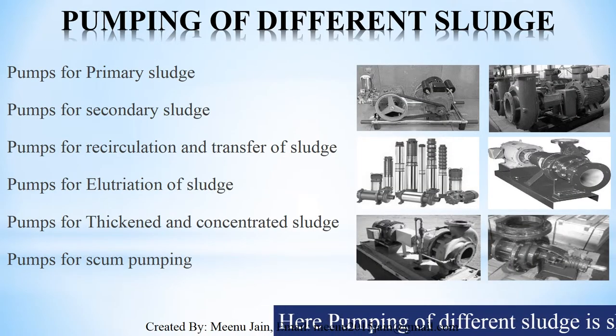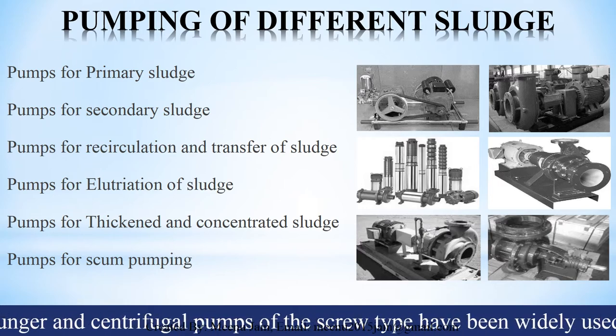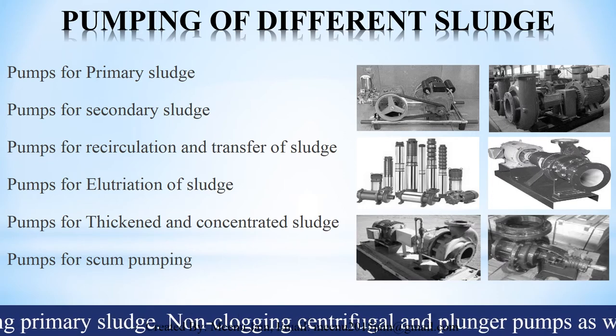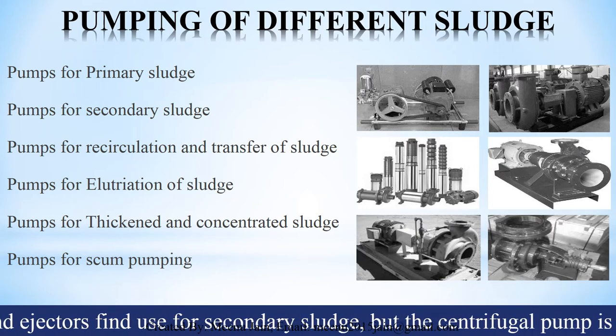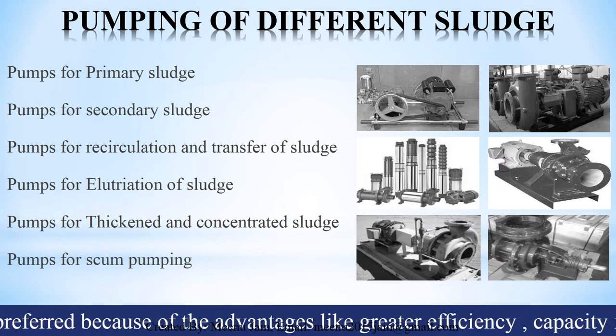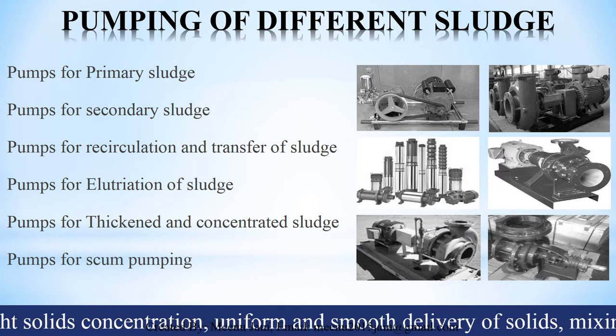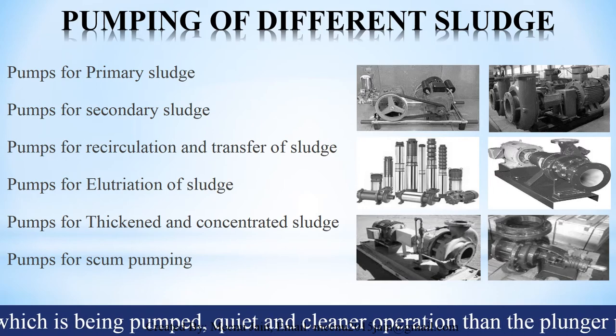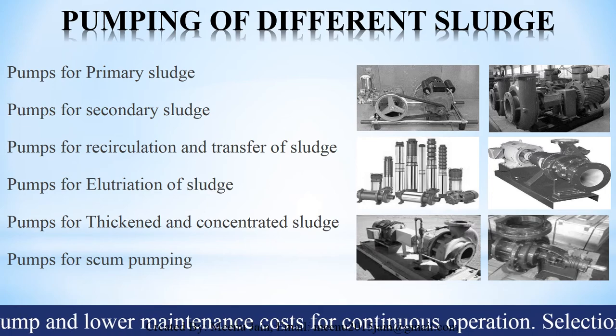Here, pumping of different sludge is shown, where plunger and centrifugal pumps of screw type have been widely used for transporting primary sludge. Non-clogging centrifugal and plunger pumps as well as airlift and ejector find use for secondary sludge. But the centrifugal pump is preferred because of advantages like greater efficiency, capacity for handling light solid concentration, uniform and smooth delivery of solids, mixing of mass being pumped, cleaner operation than the plunger pump, and lower maintenance cost for continuous operation.